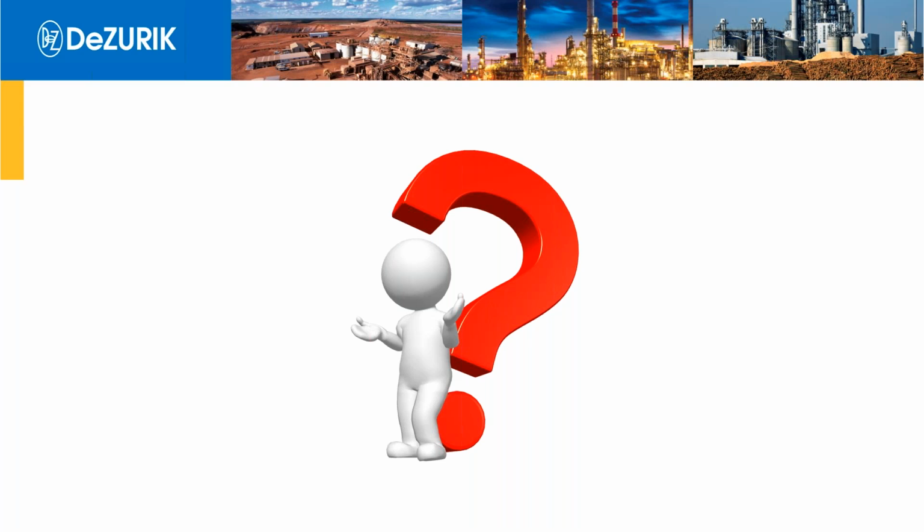So that's a broad question. I think the way I'd answer that is it depends; there's a couple factors in play there. Probably the most important factor is the media. If you have a media that is dirty or has a lot of erosives in it, sand, grit, abrasives, you would want to use a control valve that would have a clean flow path. And what do I mean by clean flow path? You would not want to use a butterfly valve where the disc and shaft are right in the middle of the pipeline, exposed to that abrasive process media.